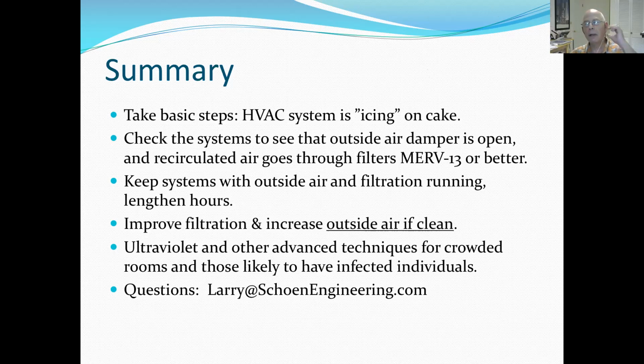Based on the China bus, would I recommend dedicated HVAC systems for sick employee rooms? I don't think sick employees should be coming to work. In hospitals, they have airborne infectious disease isolation rooms, AIIRs. If you have somebody at home who is of a known infection status or of a high-risk infection status, then we're recommending procedures like that for the home even. The overall rule, whether it's industrial ventilation or disease prevention, is air should flow from clean to dirty. You don't want air flowing from dirty to clean. So if you're trying to keep an area clean to prevent somebody from being infected, you want the air to go from that area, the clean, to the dirty. If you have an area where you know someone is infected or high risk, that's the dirty area. You want air to flow into that area and then to the outside.